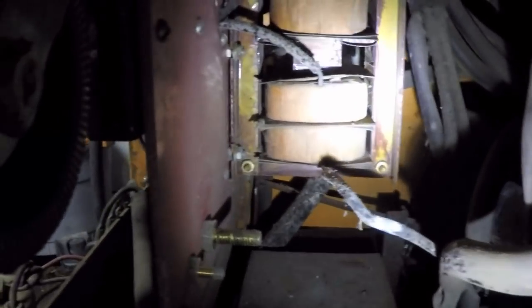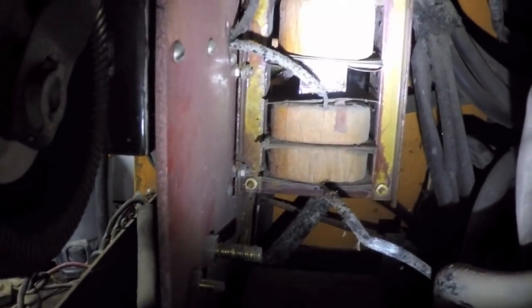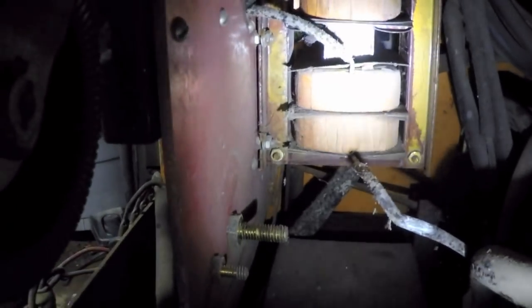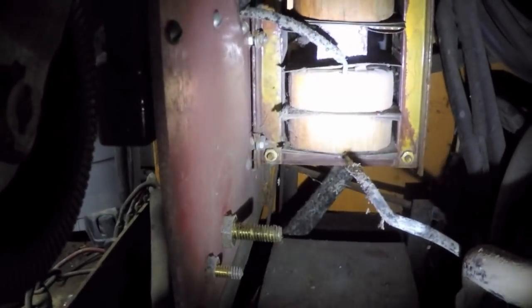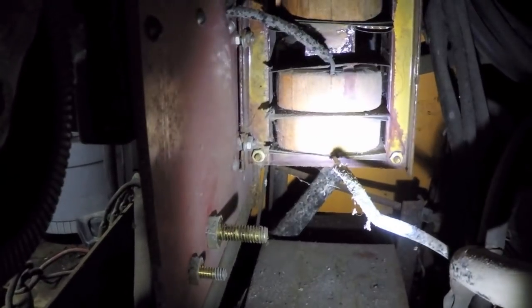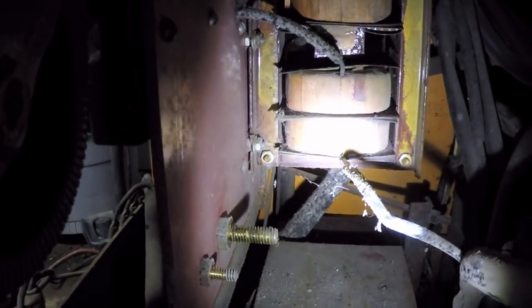Now that I got this out, I want to get back to looking at this transformer. It has a lot of corrosion on it, and part of me wonders if the transformer could be part of the problem. But I tend to think, since I have activity at the spark gap, that high voltage is coming out of the secondary of this transformer, so that makes me think it's not the culprit.